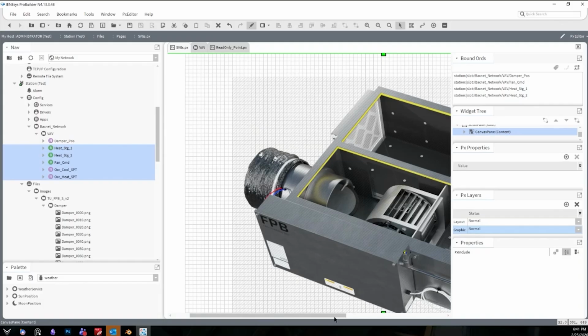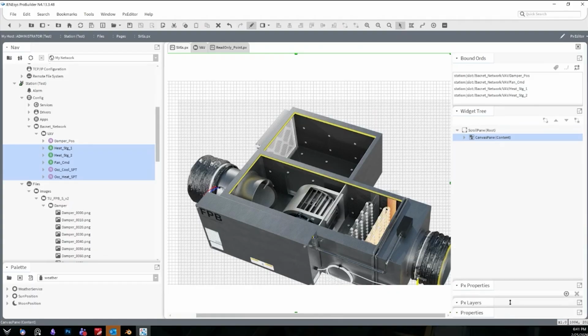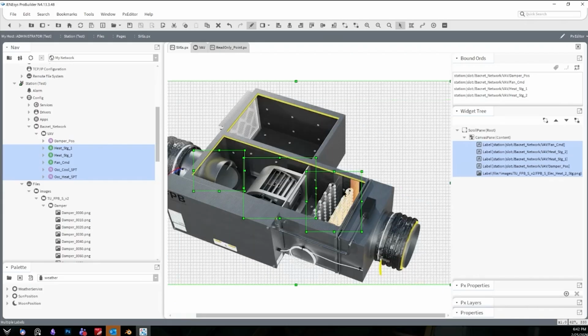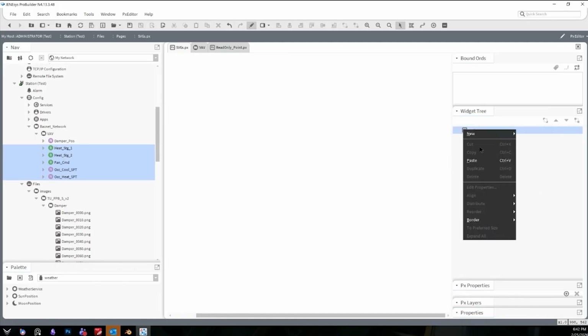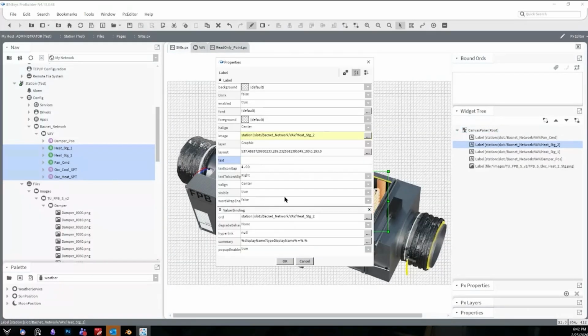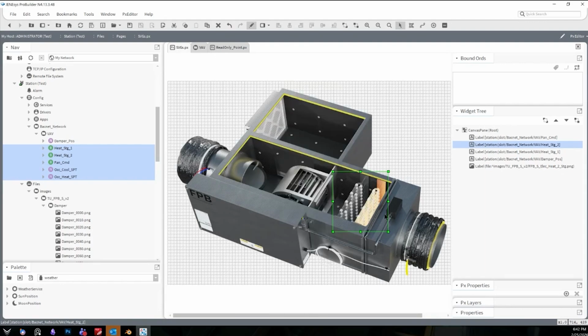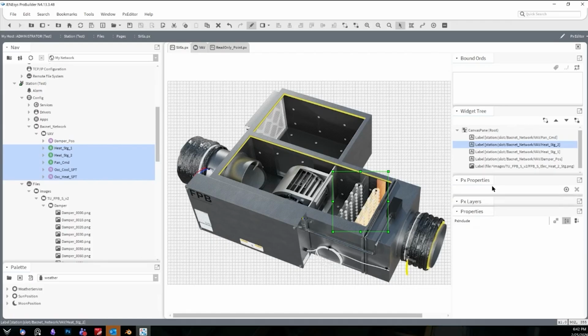Okay. Let's get out of Zoom. Let's grab everything in here. There we go. All right, we're going to cut this, delete that, and paste this. And we could make this reusable, right? If you've got a point naming convention that you stick to, that's super important. If you're going to make a reusable graphic, this can be dragged and dropped into any PX view, and then just start working with just a couple clicks.